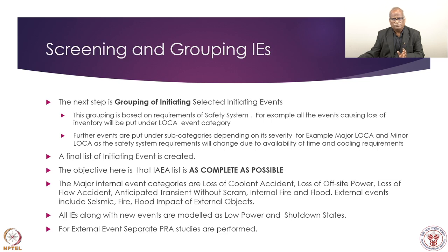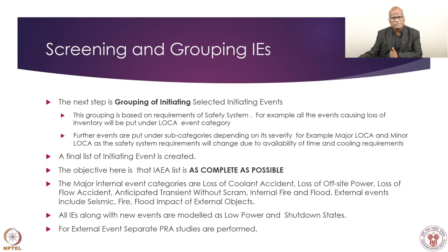After screening, the events are grouped - the grouping activity saves effort and brings clarity. Events of a similar type that need similar treatment are grouped together. For example, in loss of coolant accident there are 4 or 5 categories. If the safety system response required is the same - meaning the same event tree header events will work - they can be put under one group. Grouping is based on safety system requirements and severity. For leakage-type events there can be two categories: minor LOCA and major LOCA. The response of the safety system required will be different - minor LOCA requires certain systems while major LOCA requires additional systems with different timing.